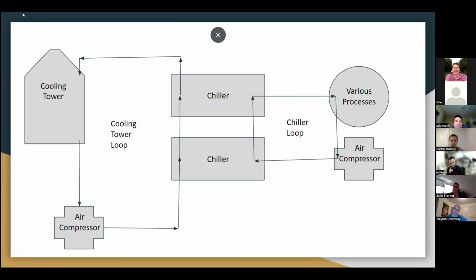you really don't need to worry about cooling tower energy use. You can almost ignore that in this entire analysis, because all you're doing is the air compressor is rejecting X number of BTUs into the chilled water loop. The chiller is taking those same X number of BTUs and rejecting it into the cooling tower loop. And the cooling tower has to reject those X BTUs of heat to the atmosphere. X is equal to X is equal to X, right? So the cooling tower energy is almost going to be a wash.